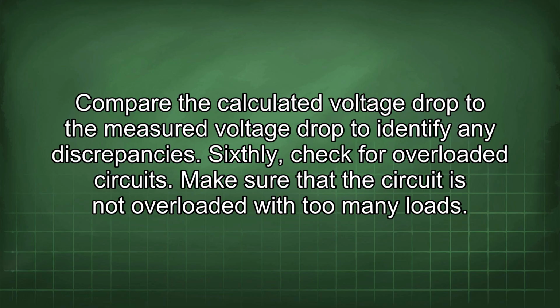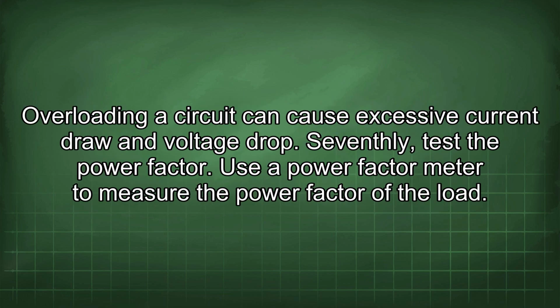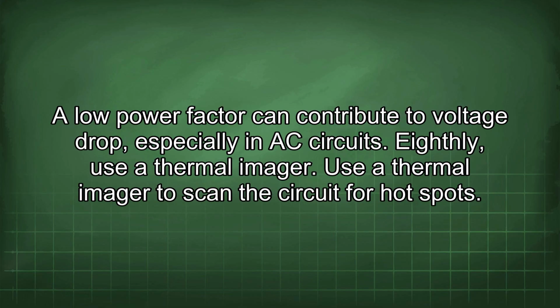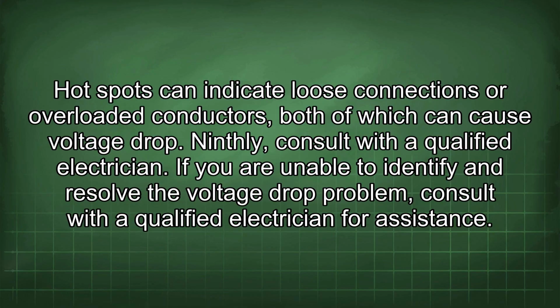Sixthly, check for overloaded circuits. Make sure that the circuit is not overloaded with too many loads. Overloading a circuit can cause excessive current draw and voltage drop. Seventhly, test the power factor. Use a power factor meter to measure the power factor of the load. A low power factor can contribute to voltage drop, especially in AC circuits. Eighthly, use a thermal imager. Use a thermal imager to scan the circuit for hot spots. Hot spots can indicate loose connections or overloaded conductors, both of which can cause voltage drop.